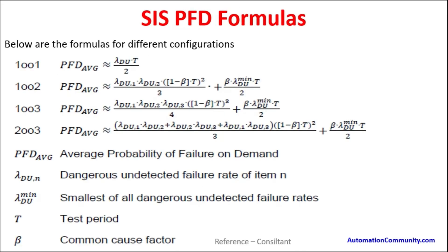Below are the formulas for different configurations — 1oo1, 1oo2, 1oo3, 2oo3, etc. Viewers can go through these formulas themselves. These are the different configurations based on which the different PFD average formulas are derived. PFD average is the average probability of failure on demand. Here, lambda_du is the dangerous undetected failure rate of each item; lambda_du_min is the smallest of all dangerous undetected failures; t is the test period; and beta is the common cause factor.